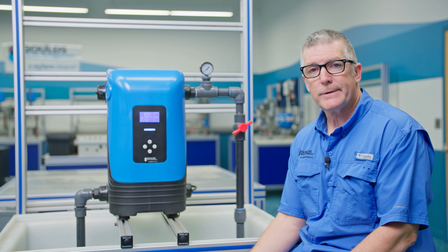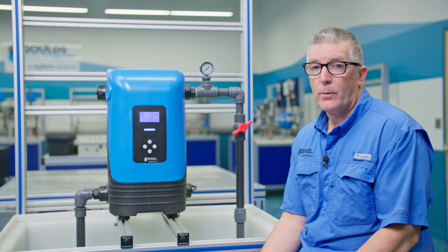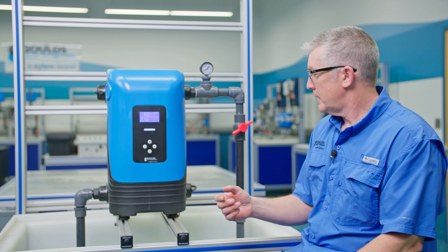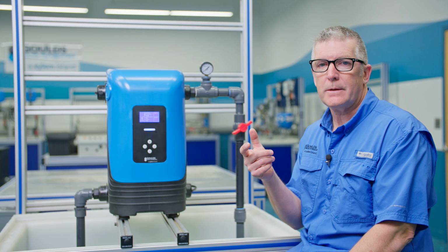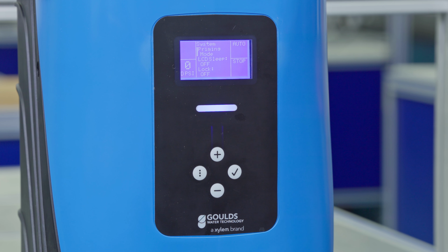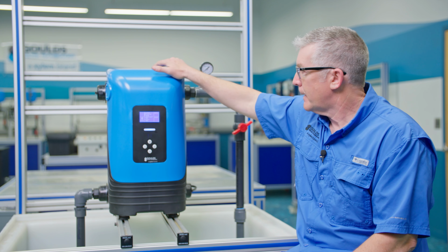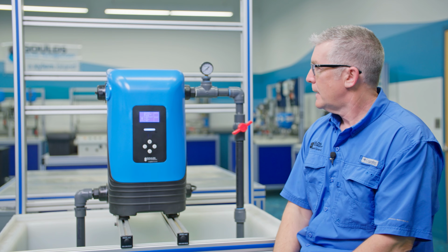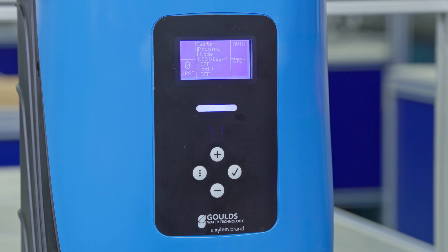So in chapter 2, we talked about, if I have a lift condition, what do I need to do? Well, I need to have a foot valve on the suction. I need to go into the back and reverse that spring, right? And make sure that spring is on the inside. So we just need to flip that. And then we need to fill the pump full of water, right? So once we've done all that, and again, in a lift condition only, then we would go in here in the system in priming mode.